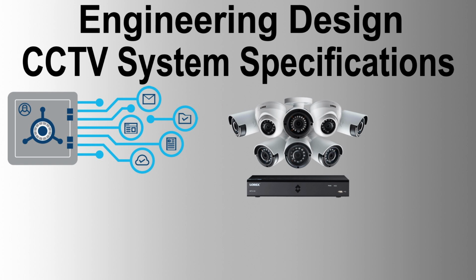The vendor is fully responsible for inspection and quality assurance of the materials and the standard of workmanship, and to perform a complete functionality test of the CCTV hardware, software, and interfaces. 100% testing of all components and functions is required for witnessing. The vendor shall fully assemble and carry out integrated factory testing of the CCTV system, including communication testing, and submit the internal test report prior to witnessing by concerned parties. The vendor shall submit FAT procedures for review and approval 4 weeks prior to the system testing witnessing.